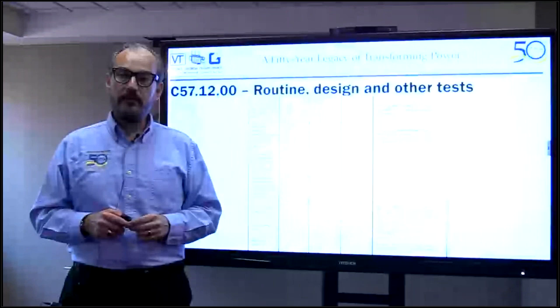Temperature rise test at minimum and maximum ratings of the first unit or first unit of a new design is considered a design test for both class one and class two. If you want your supplier to perform a temperature rise test, you must specify it in your specification. Companies that have been building transformers for over 50 years likely have no remaining untested designs, so we don't have to run it unless you specify it — but if you do specify it, we must follow your specification.